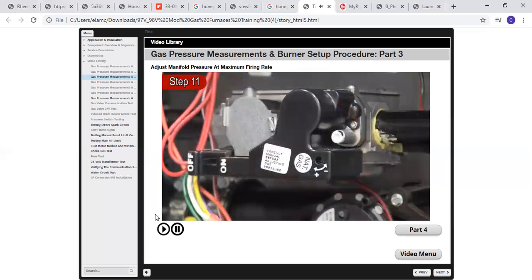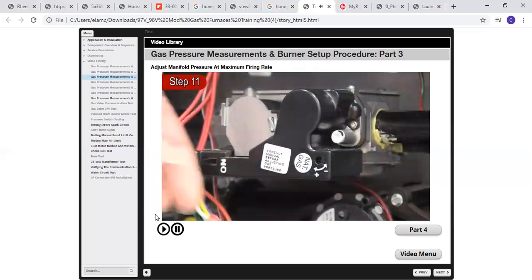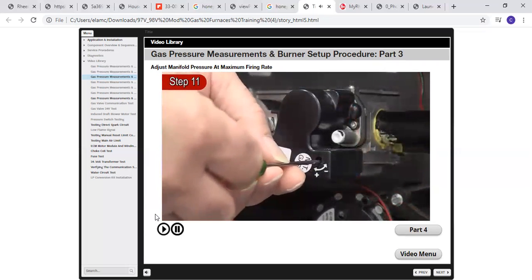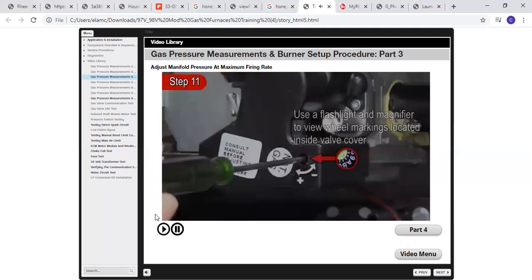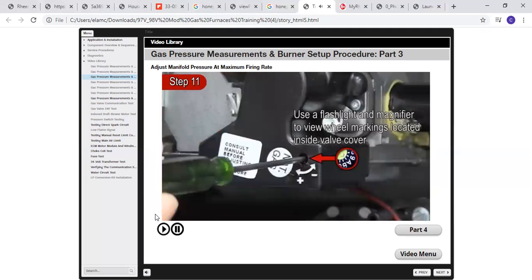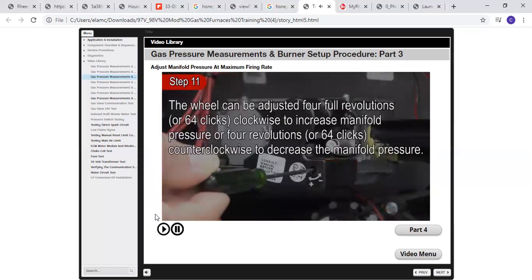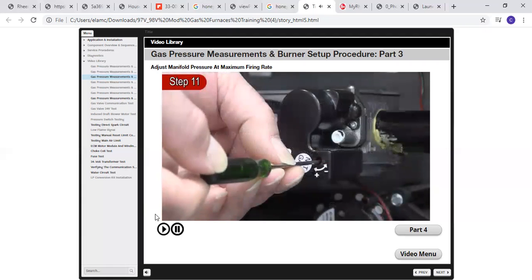Step 11. To adjust the outlet manifold pressure, insert a small slotted screwdriver into the opening at the top of the valve. The adjustment wheel is shipped from the factory in the nominal position, noted as position A on the wheel. The wheel can be adjusted 4 full revolutions, 64 clicks clockwise to increase manifold pressure, or 4 revolutions, 64 clicks counterclockwise to decrease manifold pressure. Each click is a very minimal adjustment.